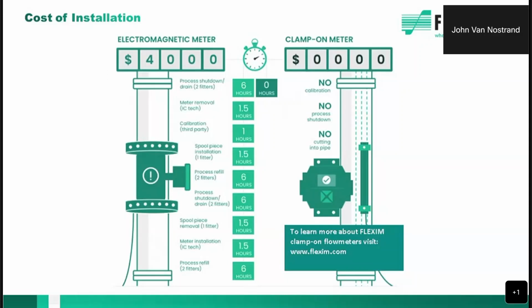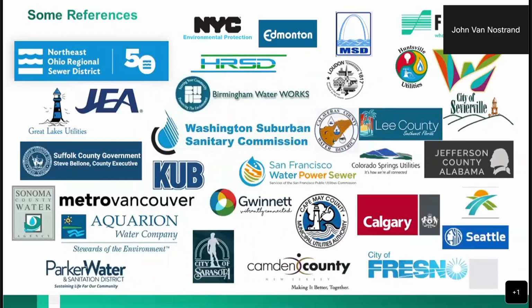So with the FLEXIM meter, we clamp right on the outside of the pipe. We don't have any downtime whatsoever. There's no calibration that you need to do. You zero it at the factory. Everything is calibrated, ready to go. You install it in the location, set it up with the proper wall thickness and diameter, and we know that we've got that correct based on the sound speed measurement. You're off and running. We've helped a lot of utility references.